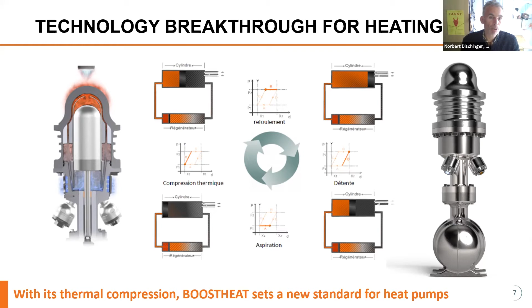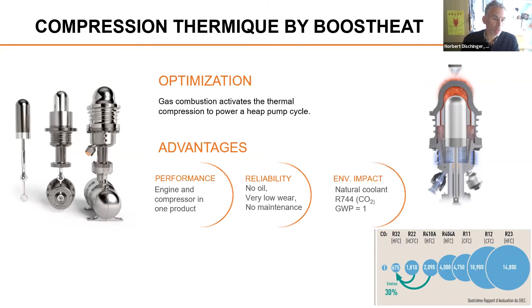So what is the reason we do that? Yes, CO2 has strong advantages regarding the climate impact. It's available all over the world. It's not depending on an industry or on specific supplier restrictions. The concept of working with CO2 and hence having a high pressure vessel system, which is designed in an intelligent way, not to make it necessary to have annual inspections, makes it easy to handle. The refrigerant circuit is limited to the compressor itself. So it's a split system, which makes it easy to install. And with the approach of having such submodules, we are prepared to ramp up quite fast. By today, we are still manufacturing in small numbers.